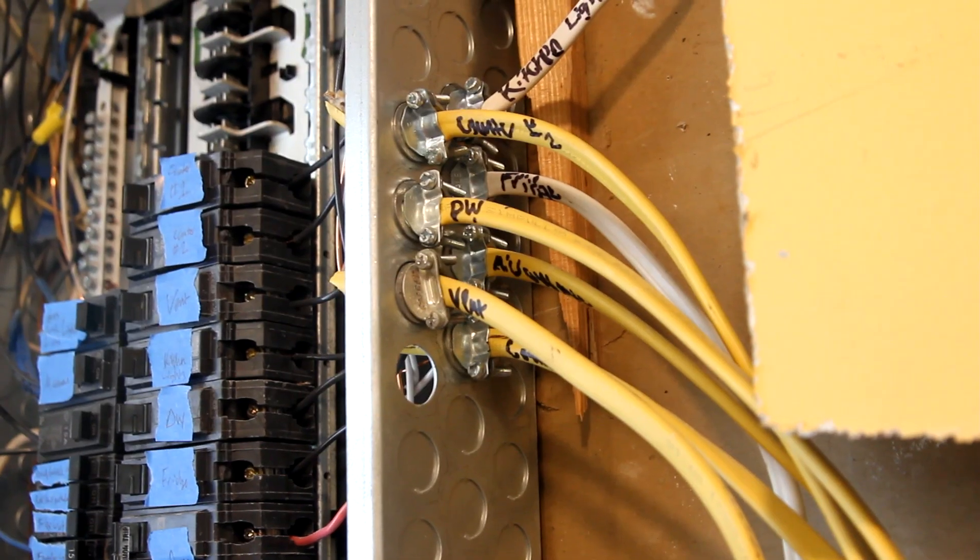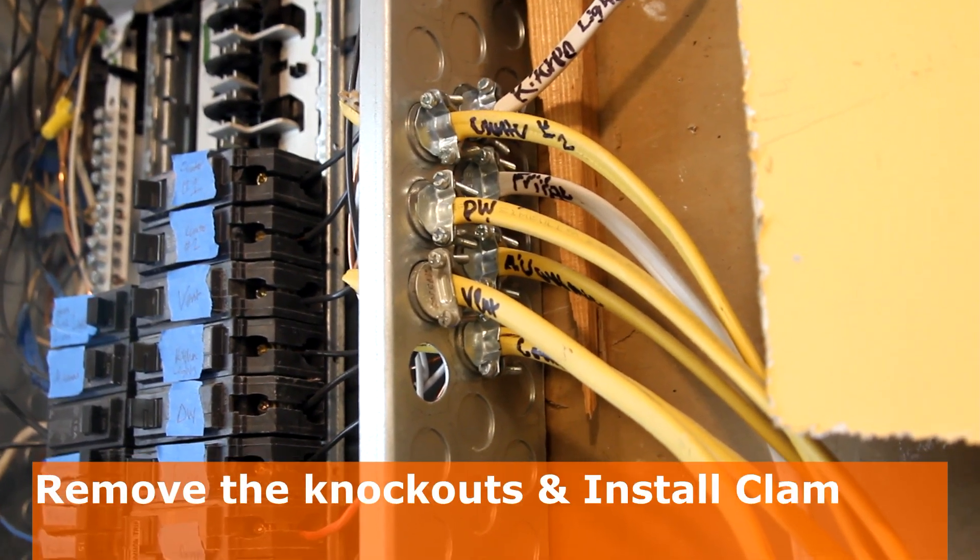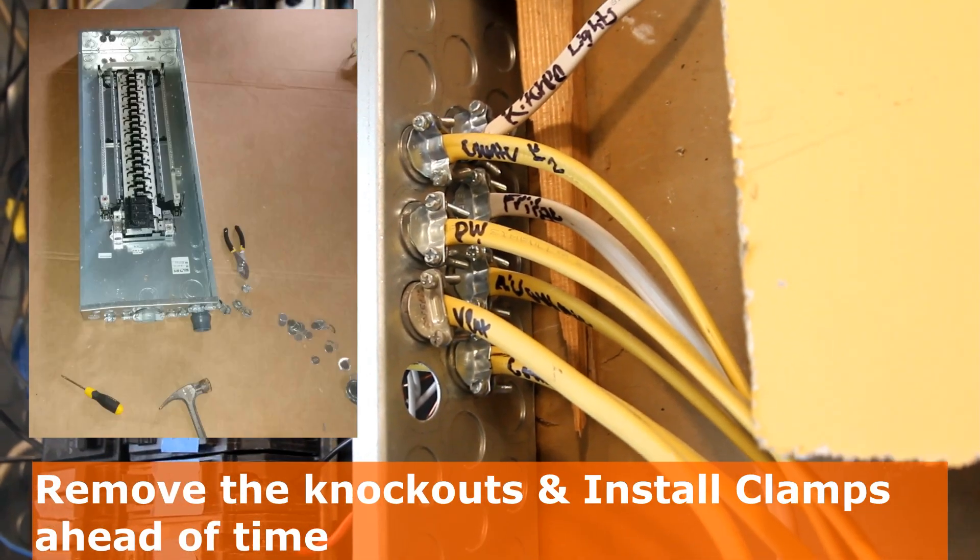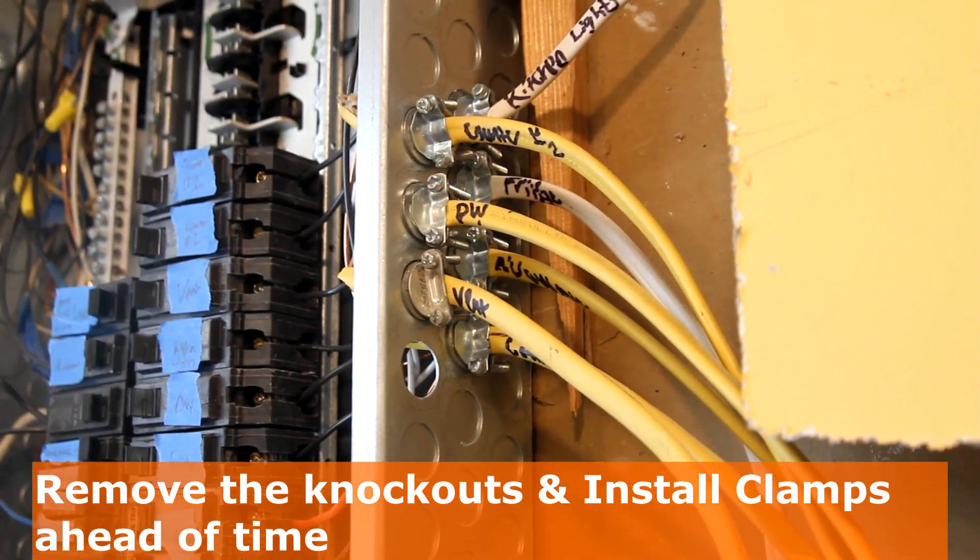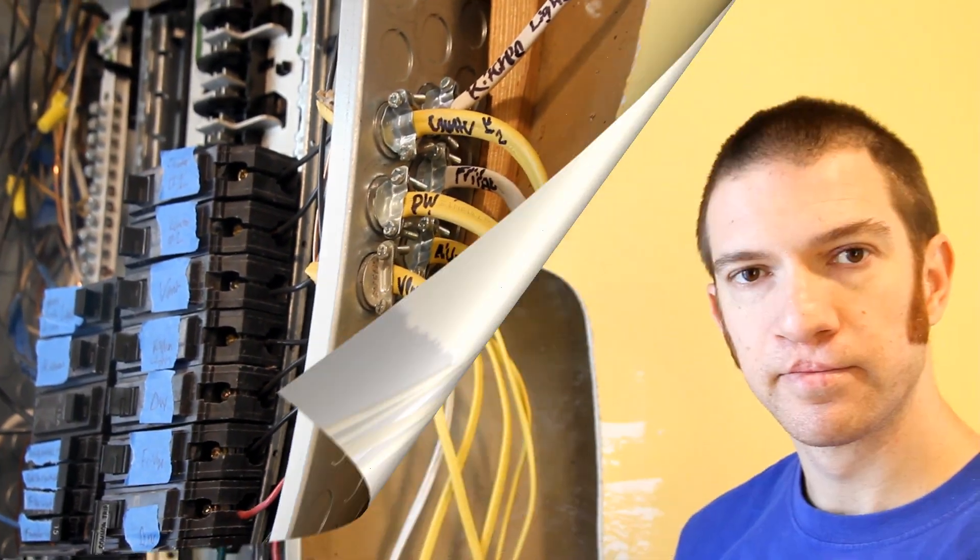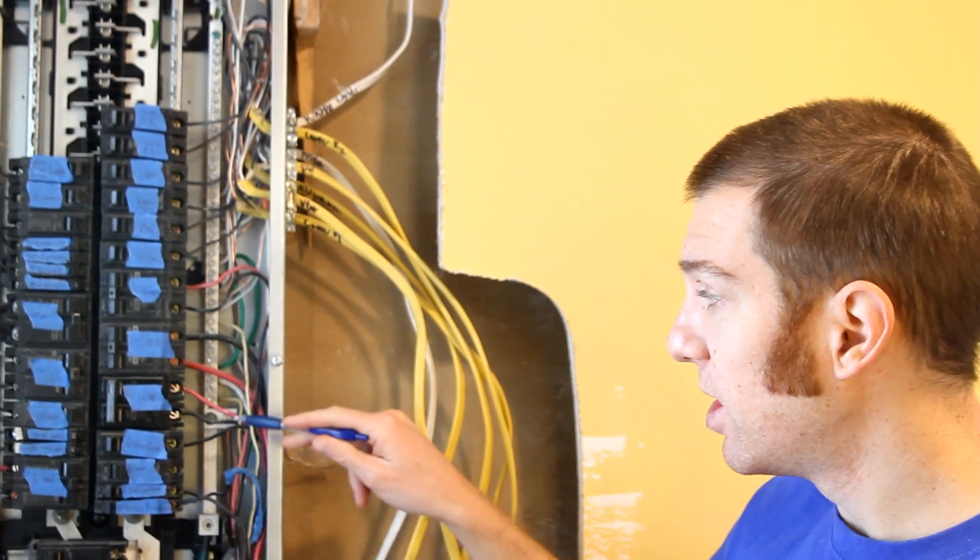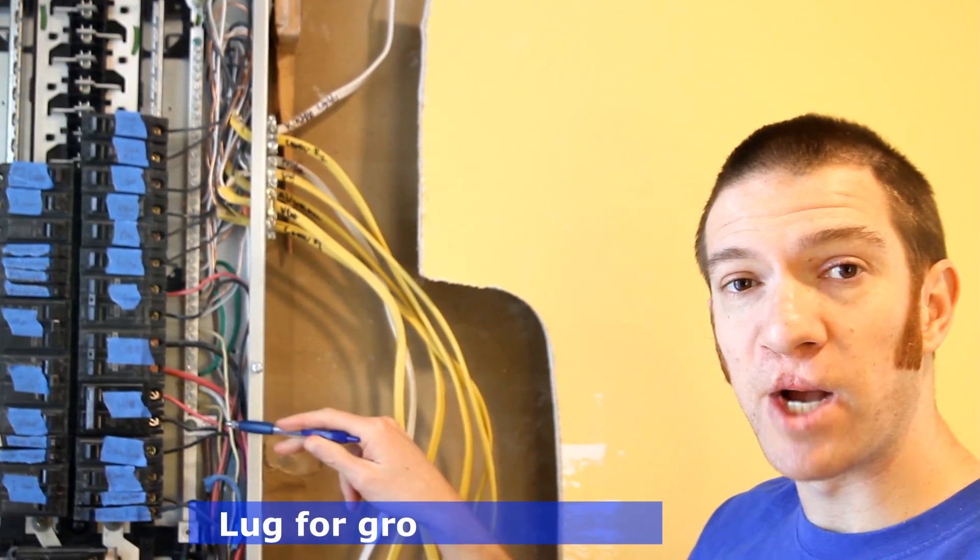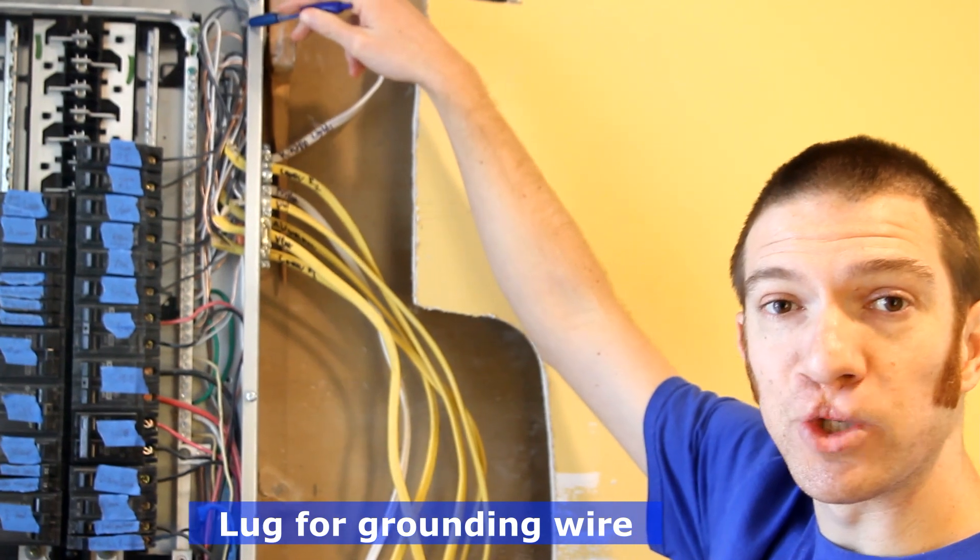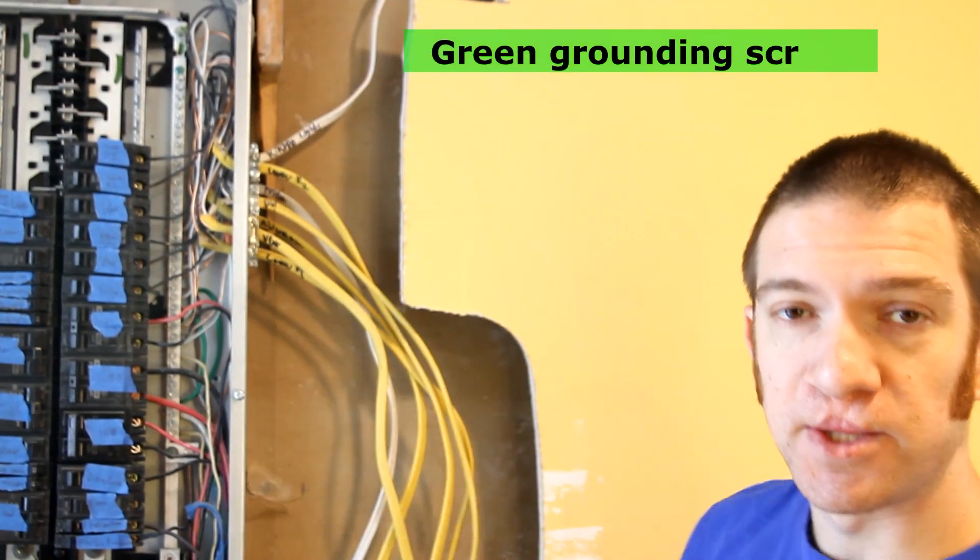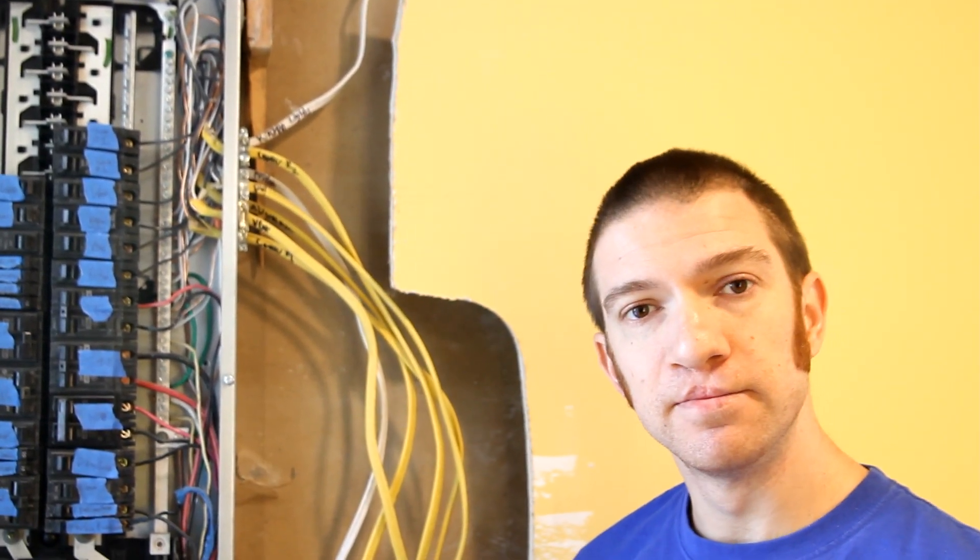Before even installing the new panel, I like to go ahead and remove a couple of these knockouts, and then I installed some of these clamps ahead of time, and that really just made things easier later. I also installed this lug to attach extra grounding rods, and then I installed this green grounding screw, which attaches the ground bus to the main panel.